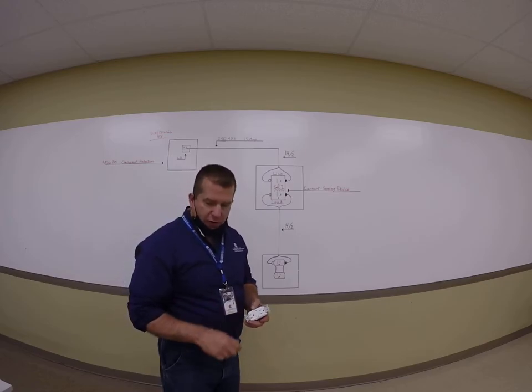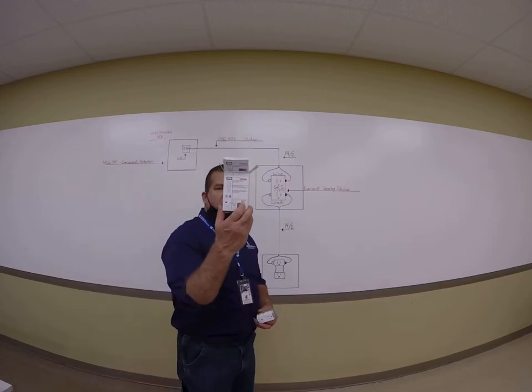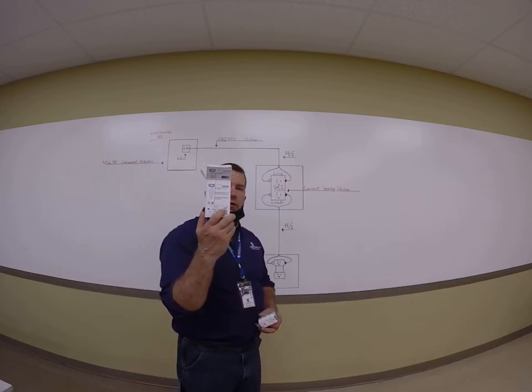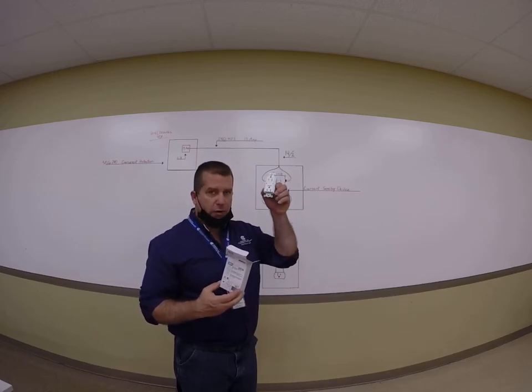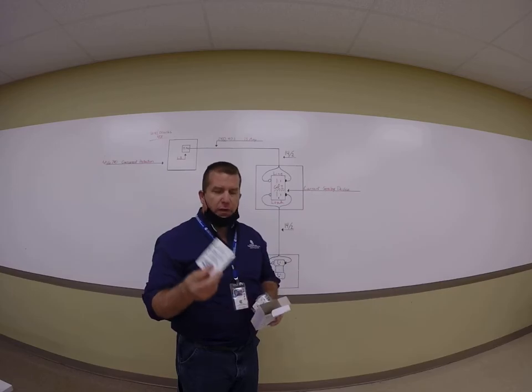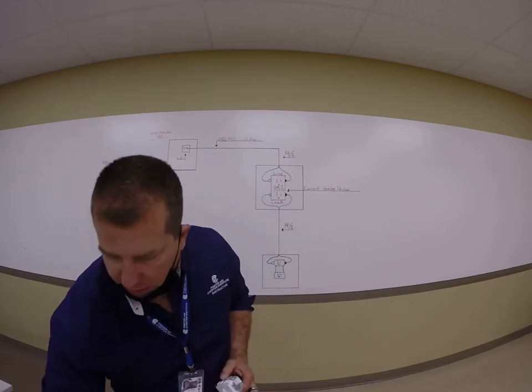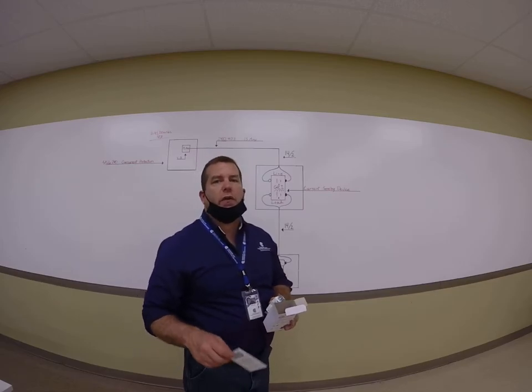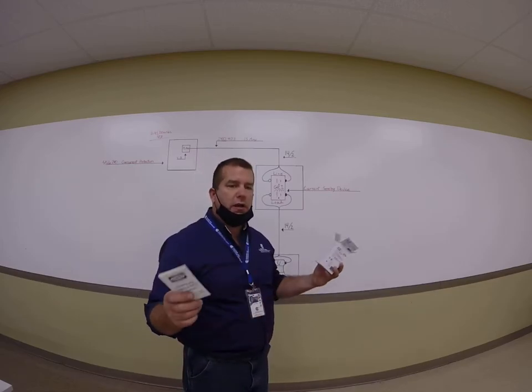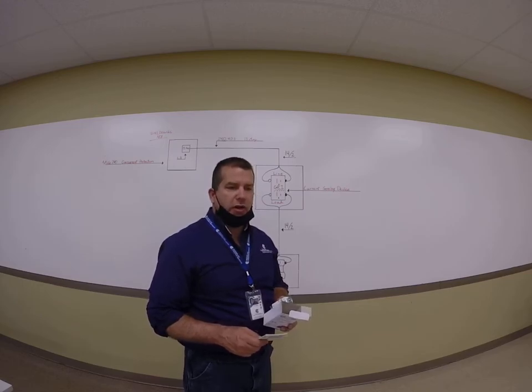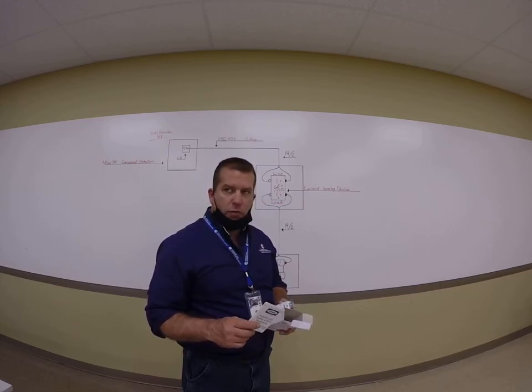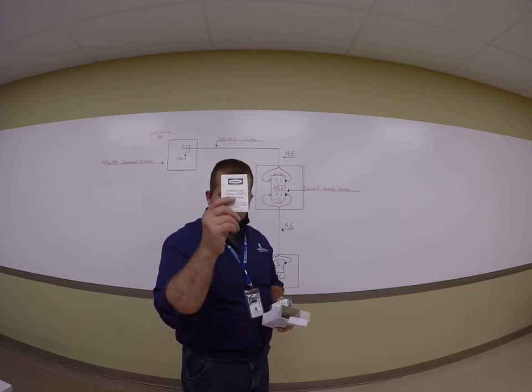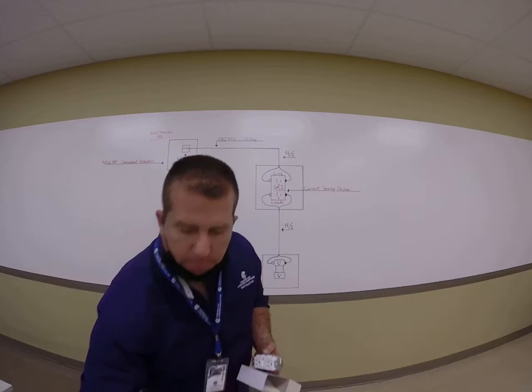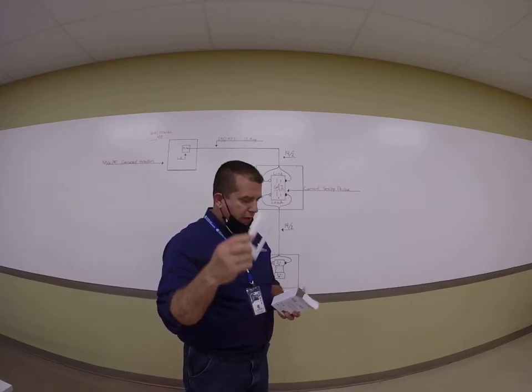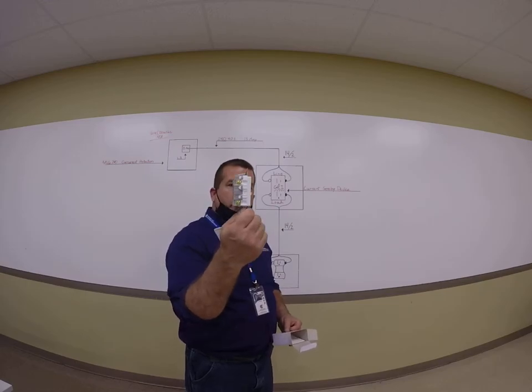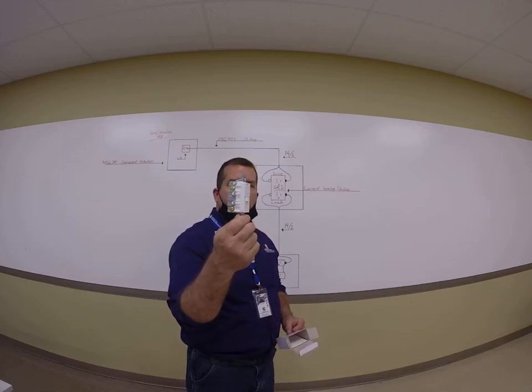So what I'd like to do first is at least present this brand new in the box. So you get a ground fault circuit interrupter. Typically you'll get something in a box like this, and then the receptacle will also be in there. And you'll also have instructions, which obviously is important because Article 110.3 in the code book requires us to make sure that we read all the applicable manufacturer's instructions so that we can properly install it according to their installation instructions. So you got a couple sets of those, and a nice finished plate. You've got two 6-32 screws that come with the GFCI, which is really nice.